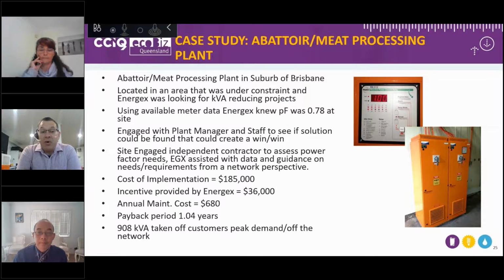of the game. What this installation managed to do is take 900 kVA off the customer's peak demand, and therefore off the network as well. So that effectively gave us 1 MVA of capacity back to the network that we could allocate to other customer needs in that local area, and it also gave the customer 908 kVA that they were no longer being charged for on a monthly basis.